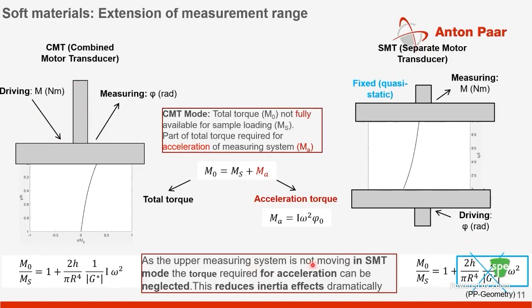So you need to use the SMT mode. If you look at the SMT mode, it doesn't really need this term, because your torque measurement is separated from where you're applying the deflection. So this reduces the inertial effects dramatically, and that's what you saw in the previous slide. Hopefully, I was able to show you that.